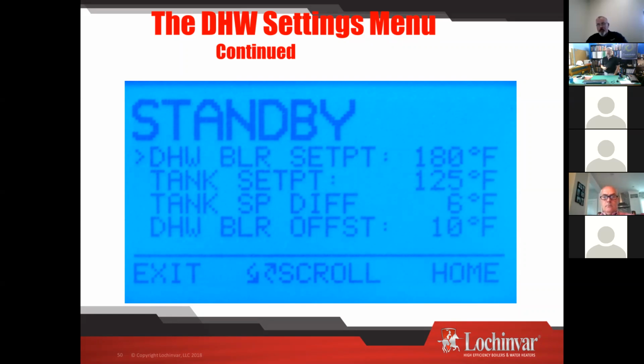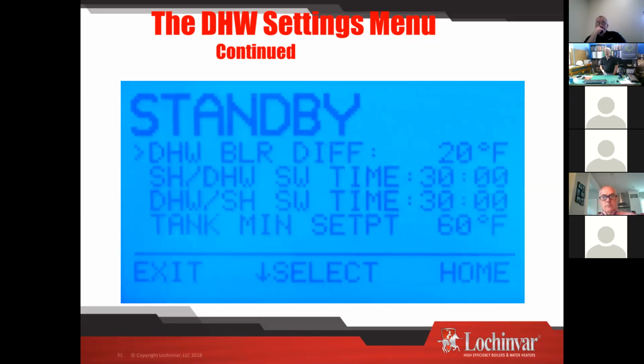The boiler offset, DHW boiler offset, works just like our space heating one did, offset and differential. How far above target do I go and how far below, okay? Domestic hot water switch times. So this is your priority override. If you have piped your indirect directly off the boiler, and you're worried about it staying in domestic hot water production mode and not heating, you can set this up right here. You can say, hey, after 30 minutes of domestic hot water production, no matter what, I want you to come back into space heating. I've only once actually seen it where somebody was using so much hot water that the boiler didn't come back, and they actually had the house start to go cold. More often than not, somebody's had a pump failure. The domestic hot water is not satisfying. It's calling, calling, calling. The boiler doesn't go back into space heating. Well, this is going to come out of the box set to go back into space heating after 30 minutes.